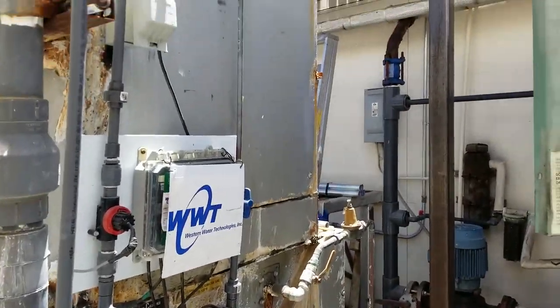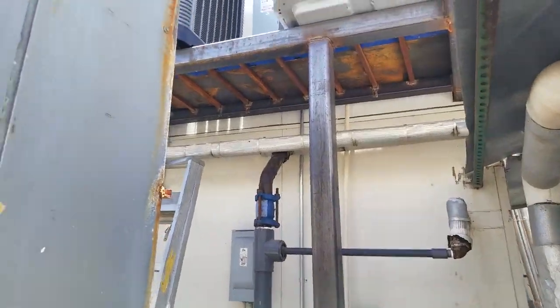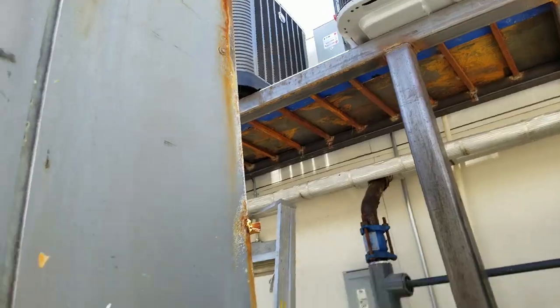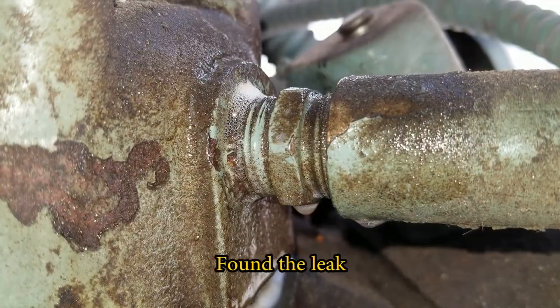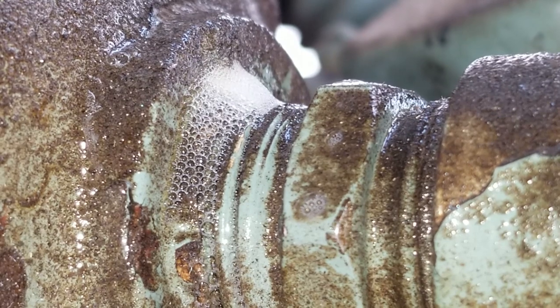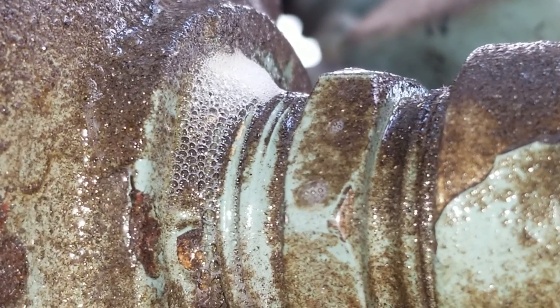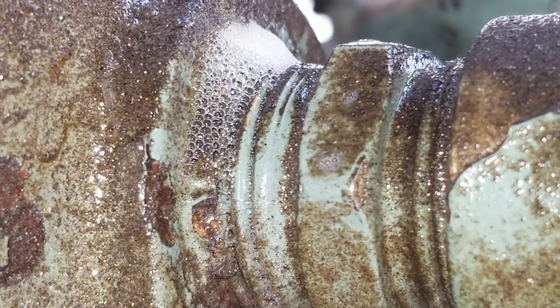I was telling the guy — I hope he doesn't get mad — but it shows like 30 inches of space required before the electrical panel, and it's against the wall up there and you've got to stand on an edge to work on that one. That's just crazy. Pretty good leak — it's already low on pressure. This is bubbling like crazy. If I were to charge it it would work, but if I left it, it would probably be days or weeks before it's down again.